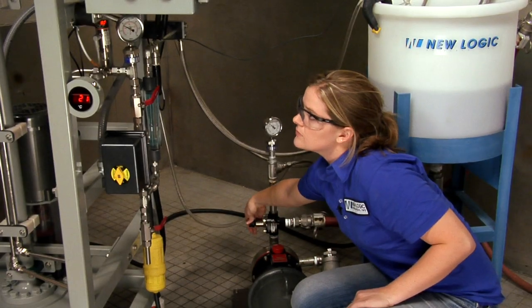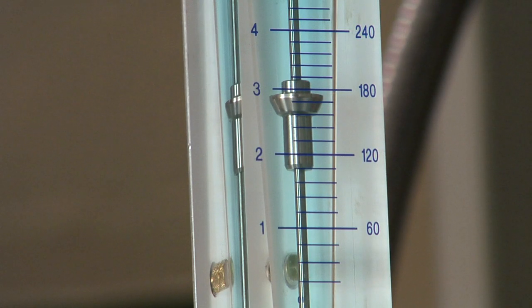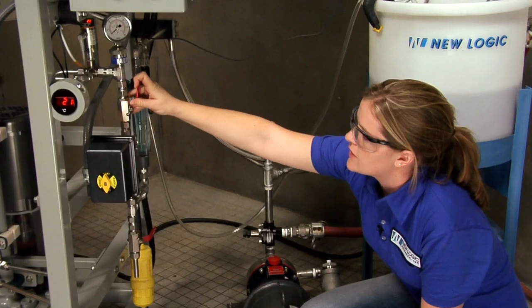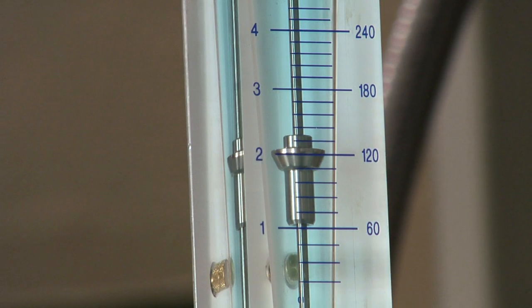While watching the flow meter, Kira is going to close the bypass valve until the flow meter reads 3 gpm. Once it is at 3 gpm, Kira is going to close the concentrate valve until the flow meter reads 2 gpm.